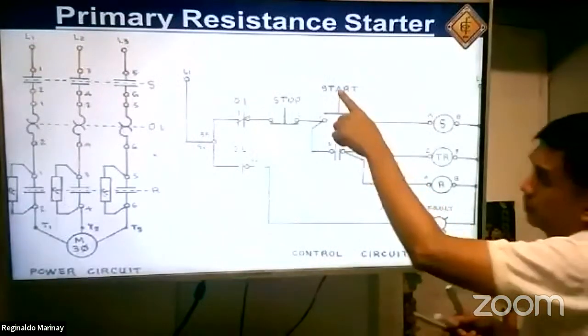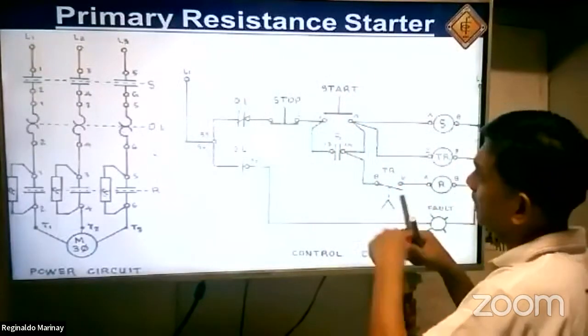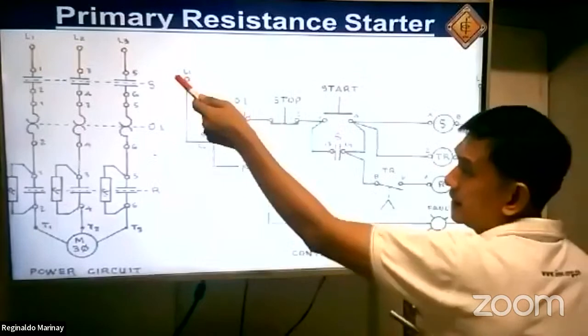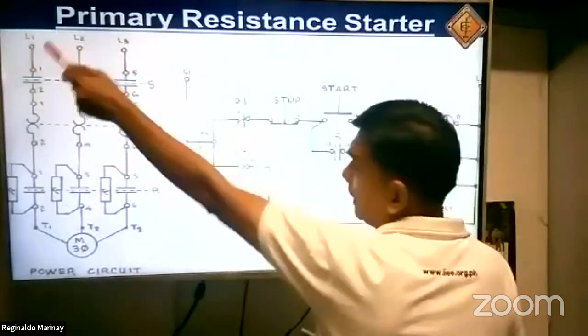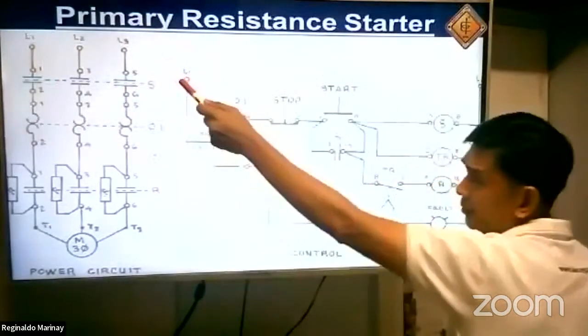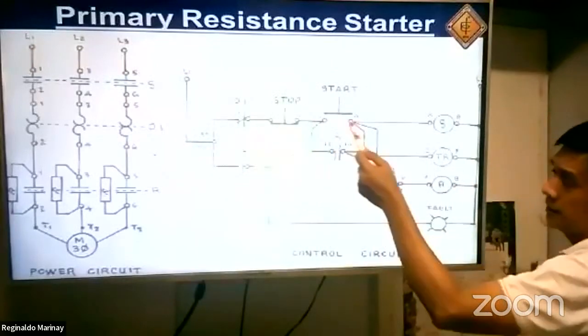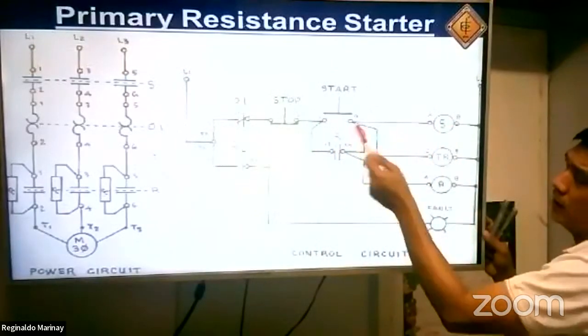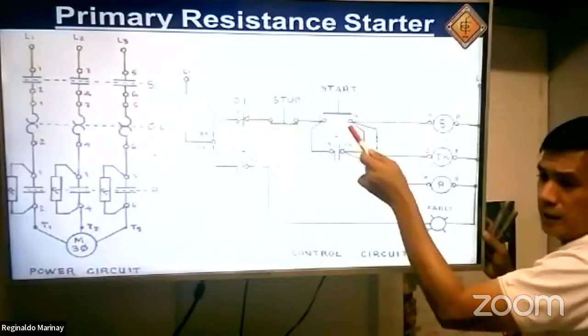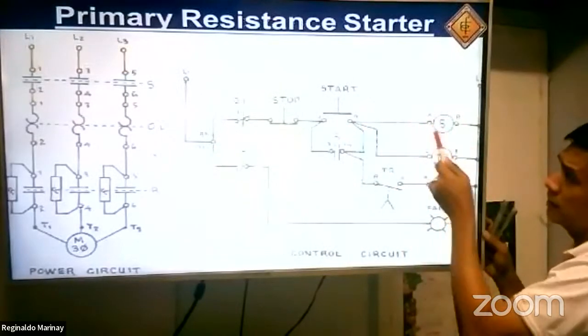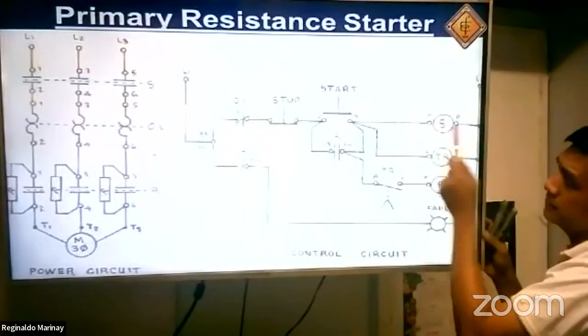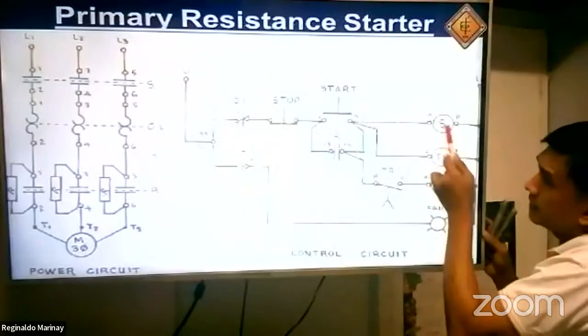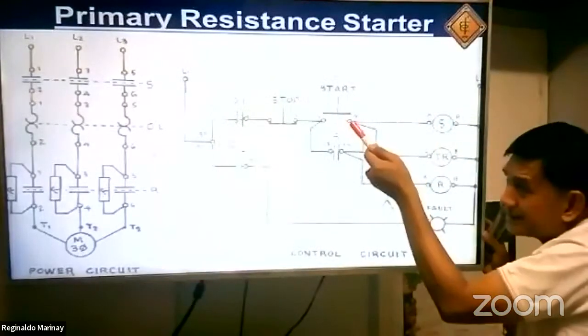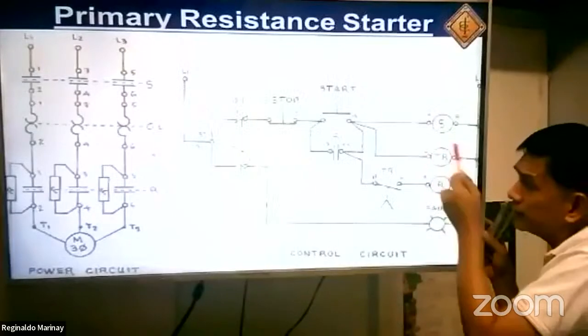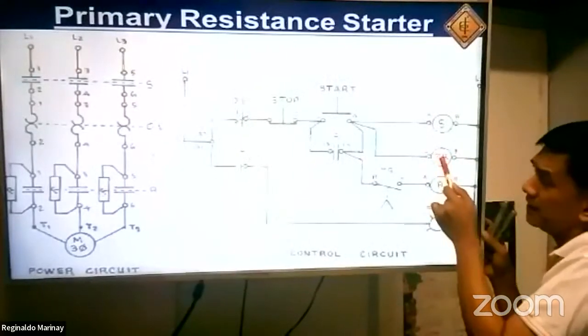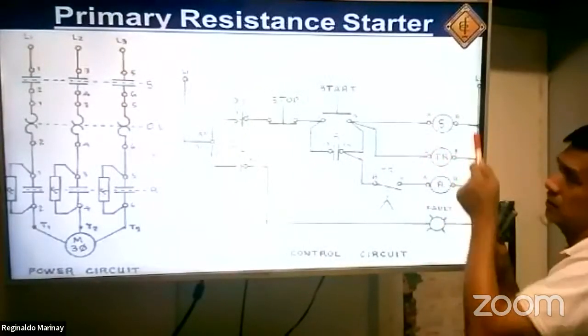We have the start button. Once we press the start button, pop, the current will flow. Of course, that is connected to line 1 and line 2 here. The current will flow here, energizing your S holding coil. Take a look here. Once the S becomes energized, the holding coil for the timing relay is energized also.